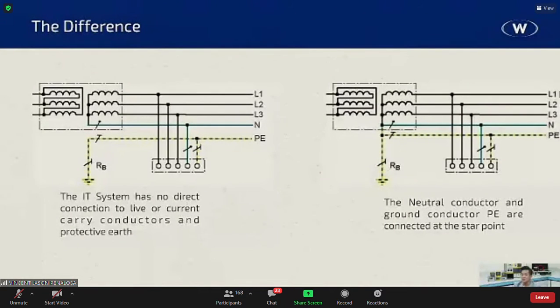That means that grounded system that we see on the screen right now, that's usually what we see in the Philippines, that we call bonded, right? All right. Now, as I mentioned, the IT system has no direct connection to live or current carrying parts. For the grounded system, the neutral conductor and the ground conductor, PE, are connected at star point. Okay, so basically, that is the main difference where you don't have direct connection to live or current carrying parts.